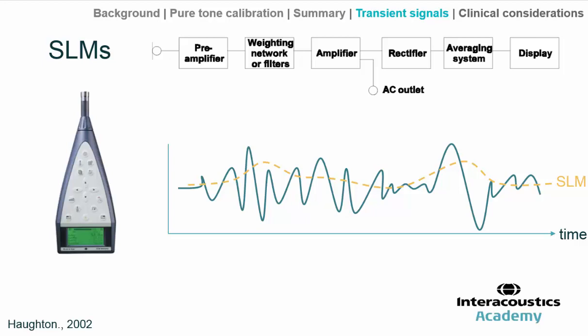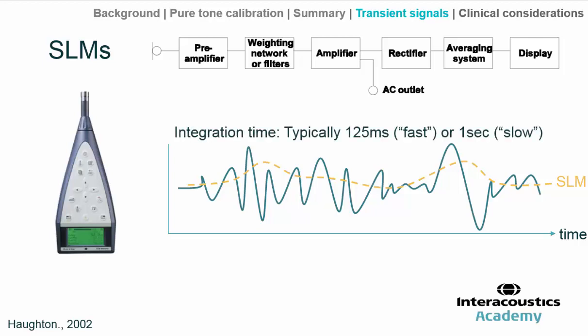There are two commonly used averaging windows or integration periods: the fast period with averaging over 125 milliseconds, and the slow period over one second. But we have a challenge when it comes to transient signals, which we're interested in for many audiological tests such as evoked potentials, because many transient signals are much shorter than even the minimum 125 millisecond integration period.